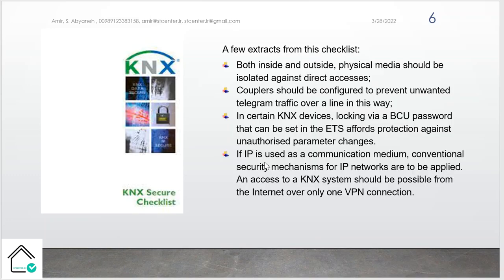The next risk is if IP is used as a communication medium, conventional security mechanisms for IP networks are to be applied, and access to the KNX system should be possible from the internet only over a VPN connection. So the book, or the KNX checklist, said if you want to connect to your system from the internet, it is highly recommended to use only a VPN connection.